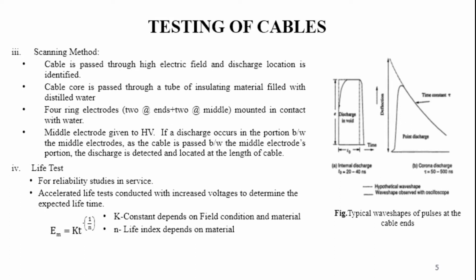Accelerated life tests using increased voltage are performed on actual cable lengths. As you can see here, the accelerated life test is conducted with increased voltage to determine the expected lifetime. It is established that the relation between the maximum electrical stress Em and the life of the insulation T in hours is approximately given as Em = K T^(-1/N), where K is a constant depending upon the field condition in the material, and N is the life index depending on the material. By conducting this long duration life test at increased stress, the expected life at the rated stress may be determined. So these are the different types of tests which are conducted on the cable.